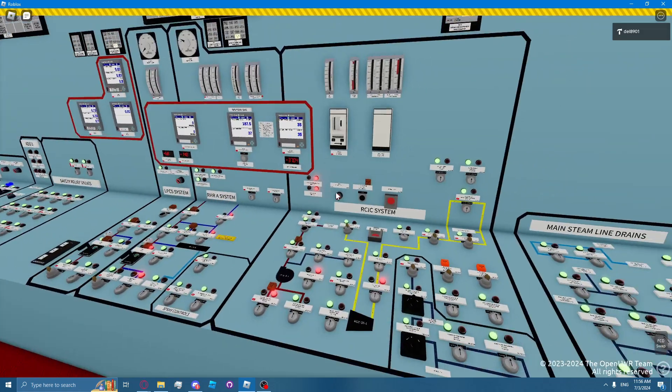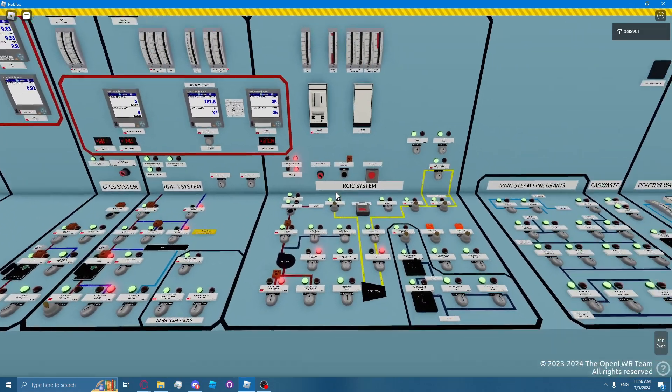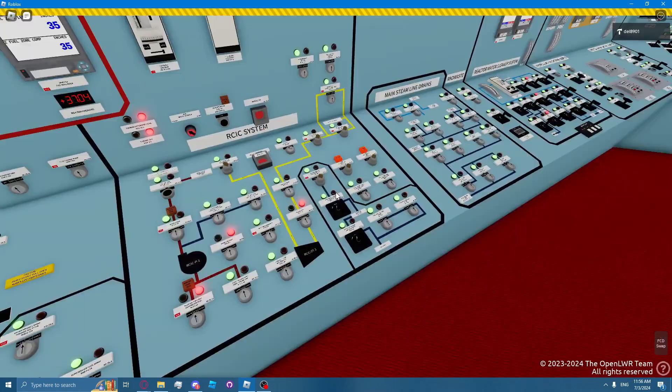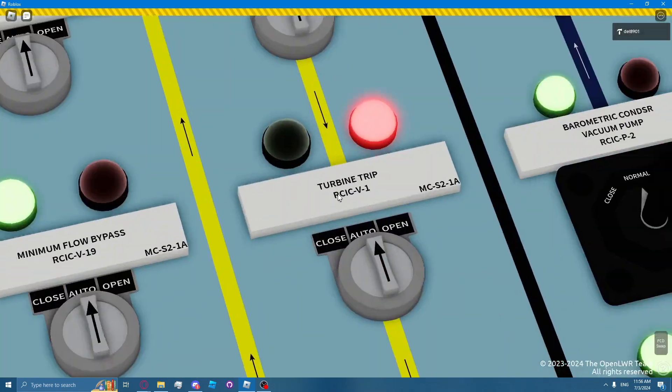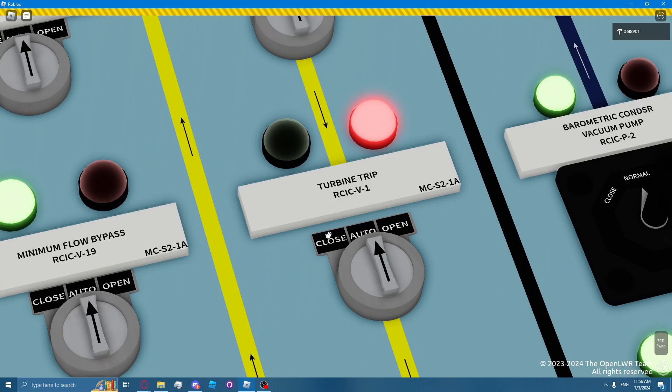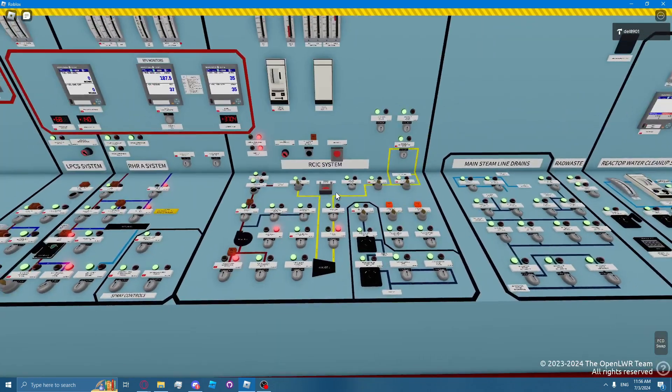In order to reset a RCIC turbine trip, the operator must take the actuator for RCIC valve 1 to close, wait for it to fully close, and then reopen it.